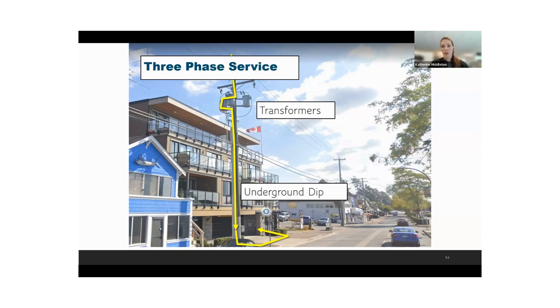We can't have long service feeds due to voltage drop. We're obligated by national standards to provide a certain voltage level or quality of power at the utilization point for the customer when it comes into a building. If we move the transformer further away from the building, for example down the street, we may not be able to provide the level of service we're obligated and mandated to by these national standards. This causes problems for the customers and their loads, not being able to feed them correctly.